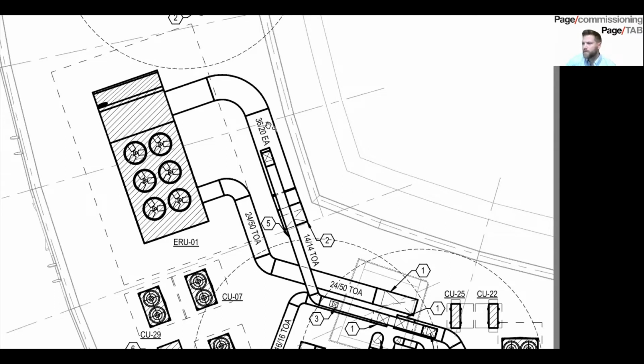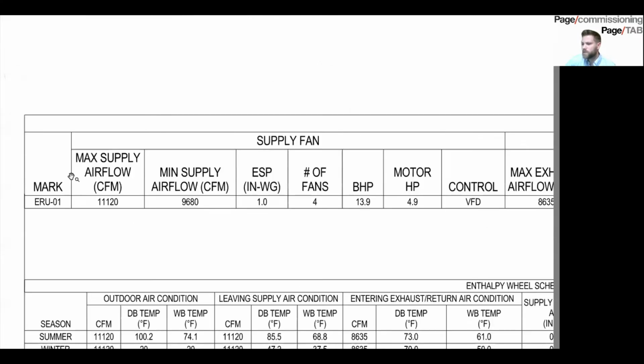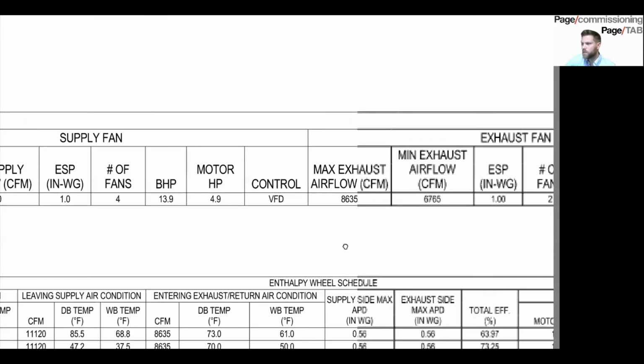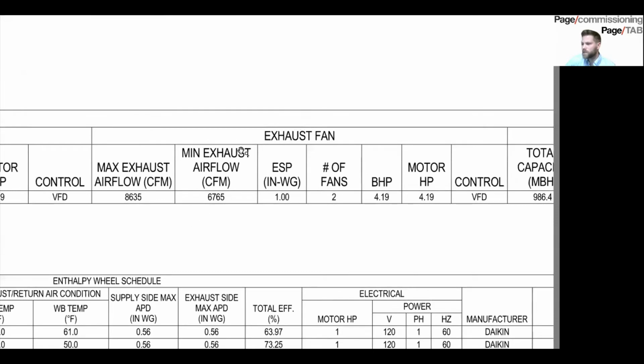So let's start on the exhaust air for this ERU1, which is an energy recovery unit. The air is coming back to the energy recovery unit, and they're saying that they need a 36x20 to deliver the air back to the unit. So I have here the schedule for this unit, which is ERU1. And then this is the supply air, which is not what we're looking at. We're looking at the exhaust, and they actually list a minimum exhaust flow of about 6,700 and a max exhaust flow of 8,600. So we're going to size, obviously, our ductwork for the max flow.